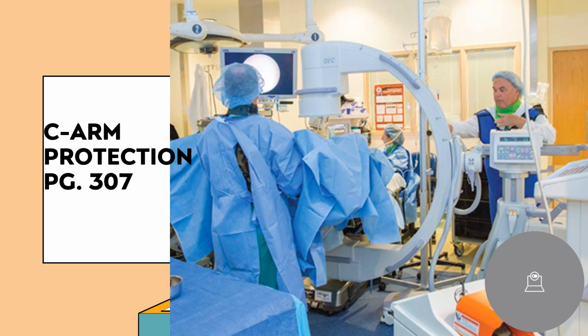The next thing that we're going to be talking about is C-arm protection, and this is going to be on page 307. So we need to be more aware of radiation safety when using the C-arm. The patterns of use are unpredictable due to the physicians requesting specific images. They are not as trained as radiologists or RTs are, so we need to help educate those who are not normally in the use of radiation practices. C-arm machines and fluoro are typically comparable, giving out several milligray in air per hour. The exposure to the RT comes from the scatter like it does in fluoro. The exposure rate caused by scatter near the entrance surface of the patient on the tube side exceeds the exposure rate near the exit surface or your image intensifier. The scatter is different by a factor of 2 to 3 times.